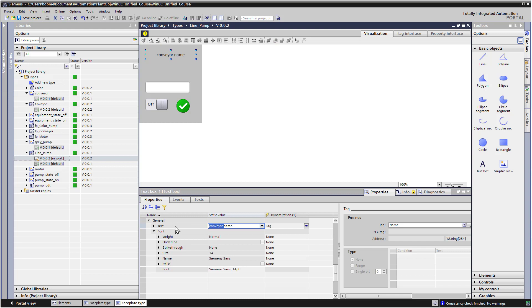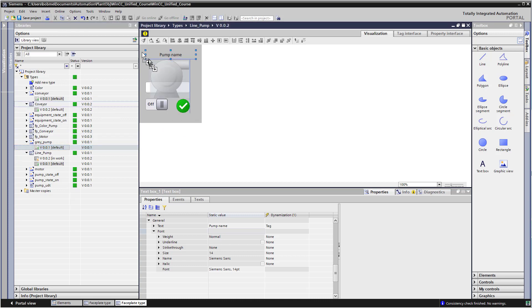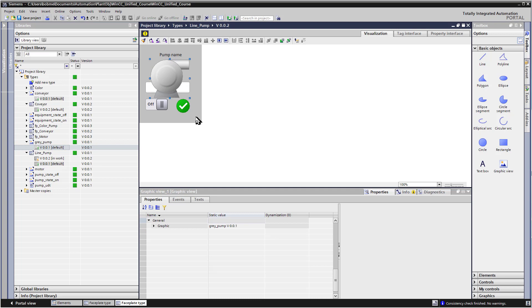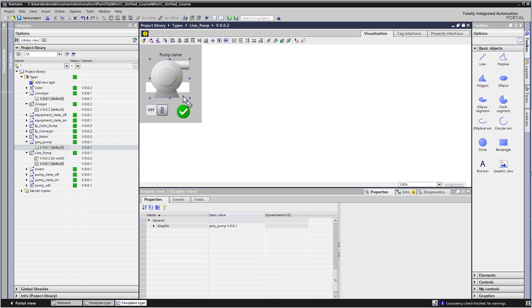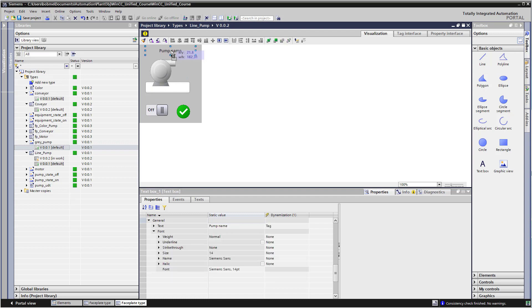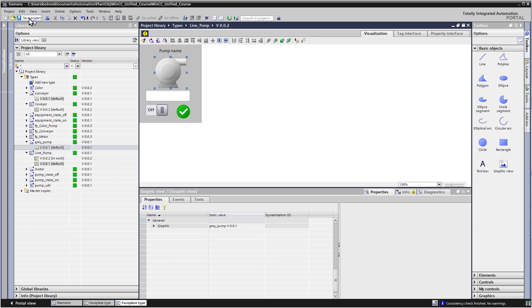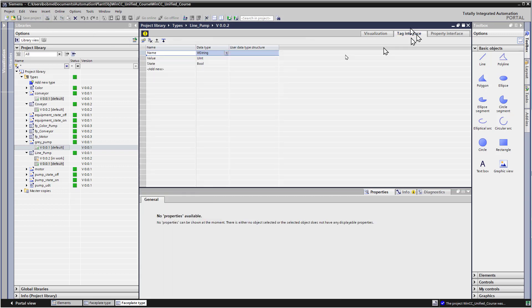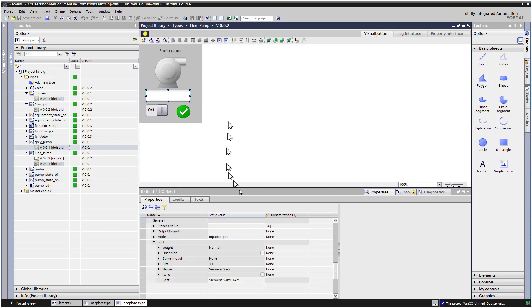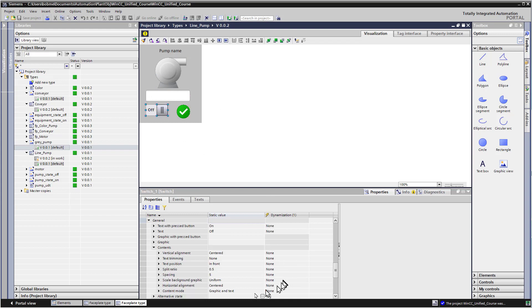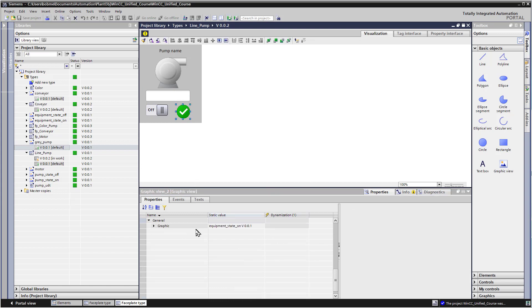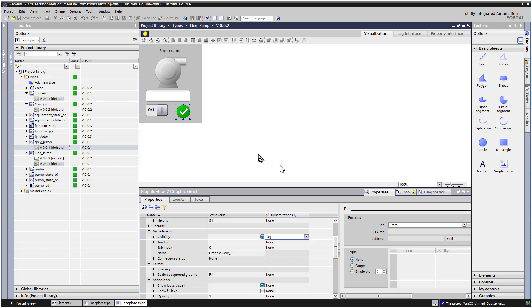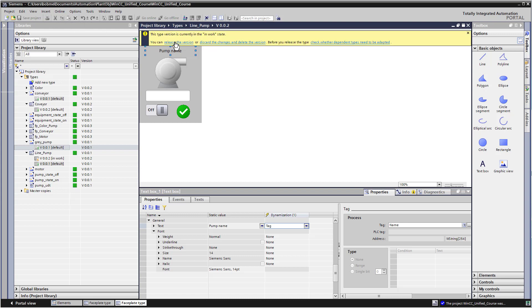And then for this text, this is going to be our pump. So I'm just going to change this to pump name so that there's no confusion. I do have a graphic for a pump in here. If you don't, you can just go add new type and add a pump graphic of your choice. But I'll just pop this in here and I'll do a little bit of refactoring. I'm just going to kind of move this stuff down, make the pump graphic a little smaller, bring my IO field down, and I'll hit save there. And just looking at our tag interface, we've got name, value, state. Looking at the visualization, of course, your IO field, the process value is still set up to tag. Your switch alternative state is still set up to your state tag, as is the visibility. It's set up to state. And then, of course, the label up here is set up to your name. So we can just touch the icon here and release this version.